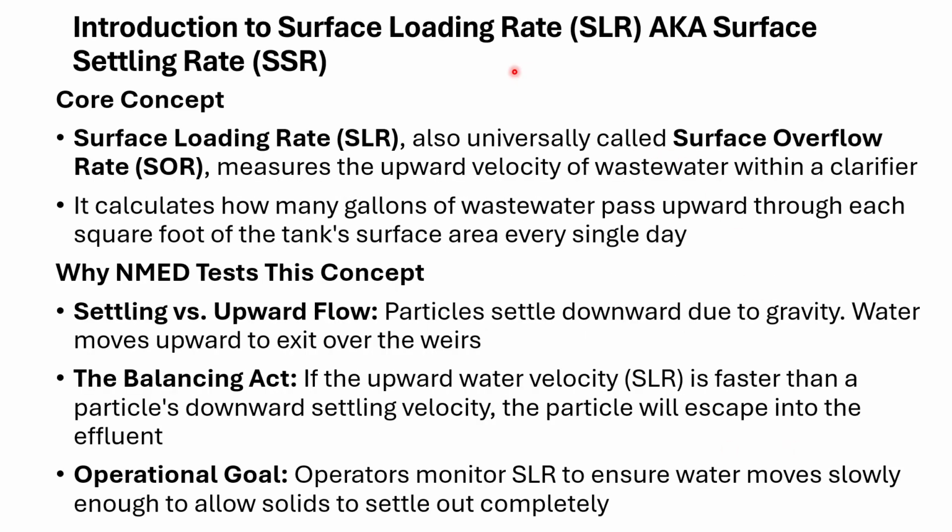Let's now switch gears to the next metric or performance measure of a clarifier, and that's the surface loading rate, or also known as the surface settling rate. Those are interchangeable, okay? So the concept is the surface loading rate, or surface overflow rate, measures the upward velocity of wastewater within a clarifier. And we're looking at how many gallons of wastewater pass upward through the square foot of the tank surface area every single day.